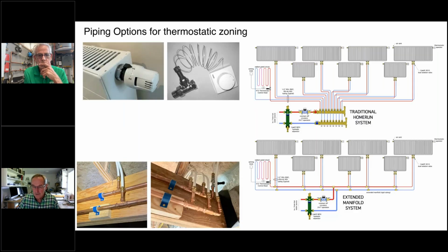What we've got here, instead of running all this PEX, we ran copper tubing along the main girder of the house. This is just 3/4 inch copper. And then in the same joist cavity that would line up with each radiator, we just stubbed out with 1/2-inch copper, transitioned over, in this case, to 1/2-inch PEX, aluminum PEX. And then these just run through those joist cavities and then pop up through the floor to the panel rads.